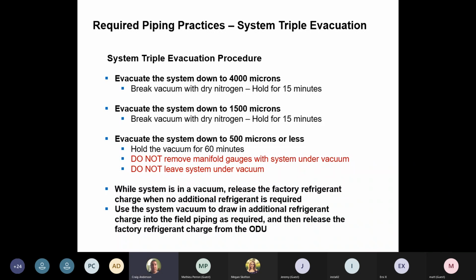Then pull it down again, bring it down to 500 microns and hold it under 500 microns. And when I mean hold it under 500 microns, you're turning the vacuum valve off, pump off, you're isolating your gauges. You'll notice your digital vacuum gauge will rise. If you're doing a new install, it's very easy to bring it down to 78 microns. The hard part is holding it there.